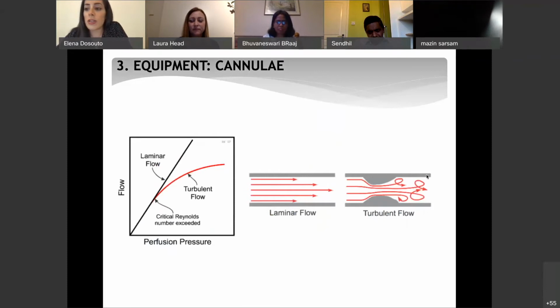So first of all, we need to estimate the patient's requirements, and to calculate what we call the flow, we look at the height and weight of the patient and find their body surface area. We use what is called the Dubois formula. Then we relate this number to the cardiac index, which I will show you. We use about 2.4 liters per minute. For most adult patients, we require a blood flow of around 3.5 to 5 liters in general.